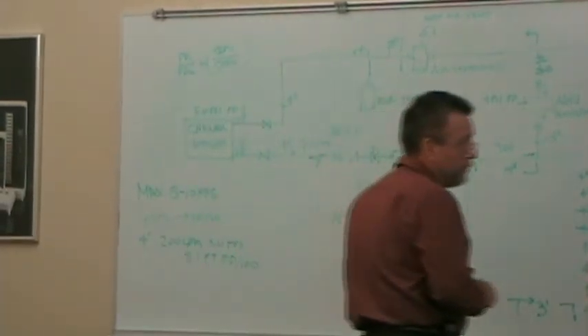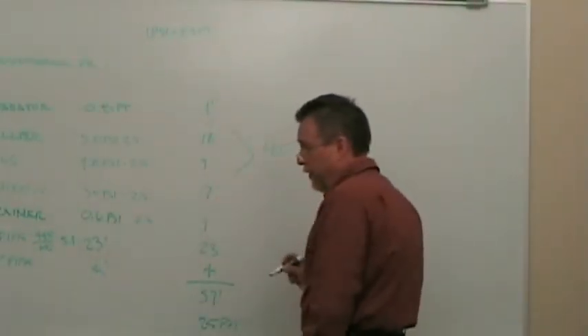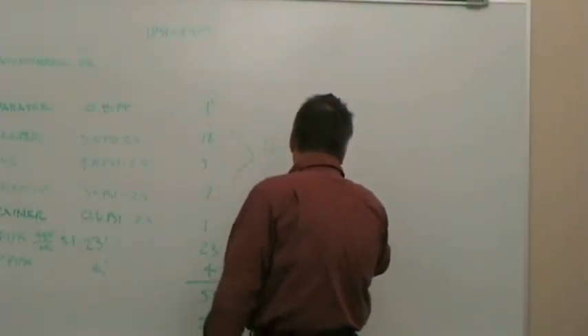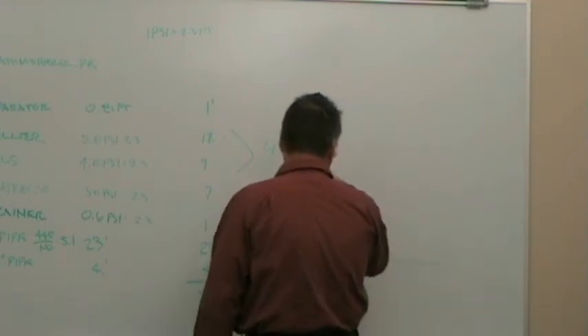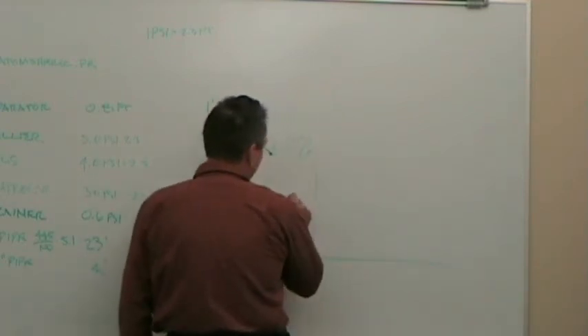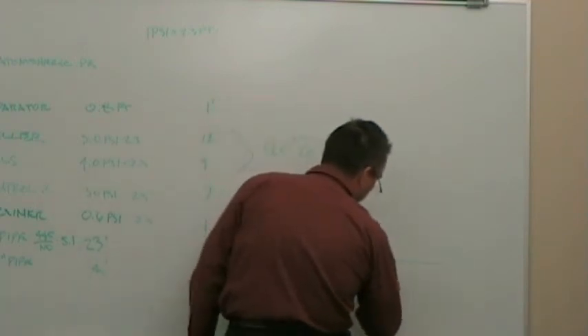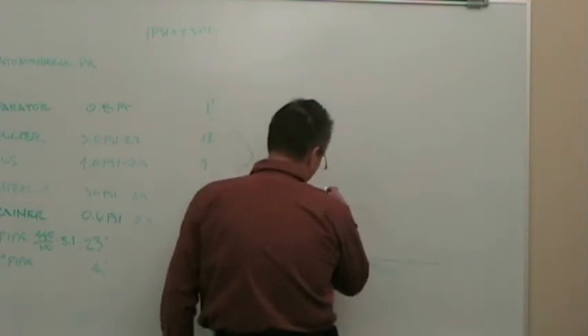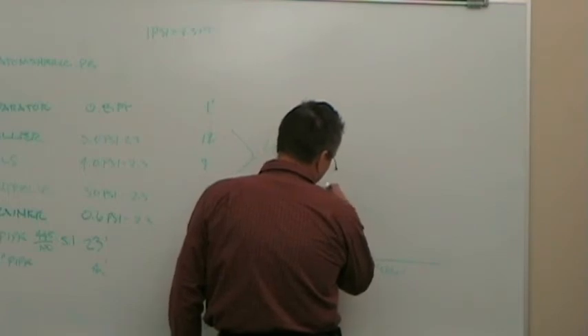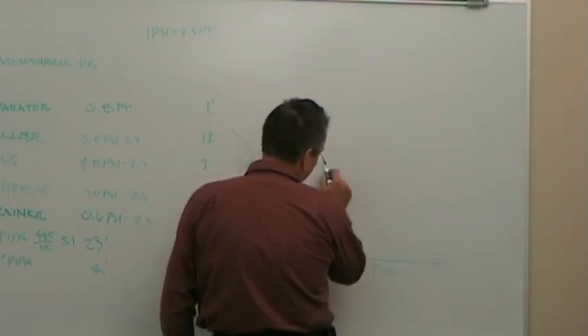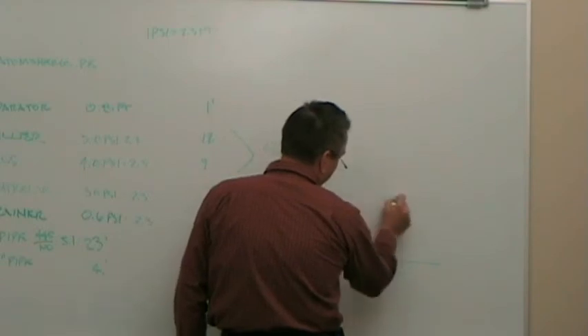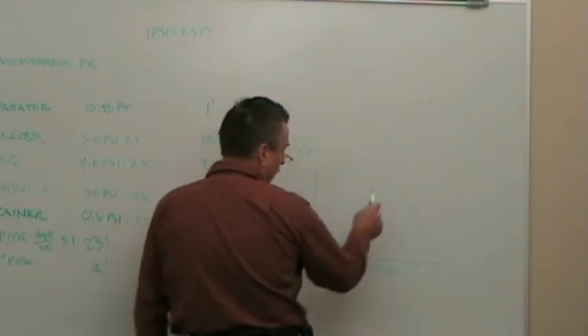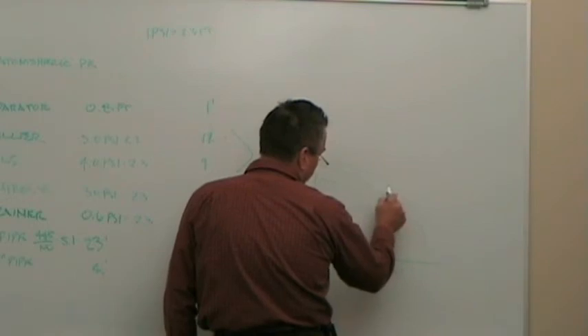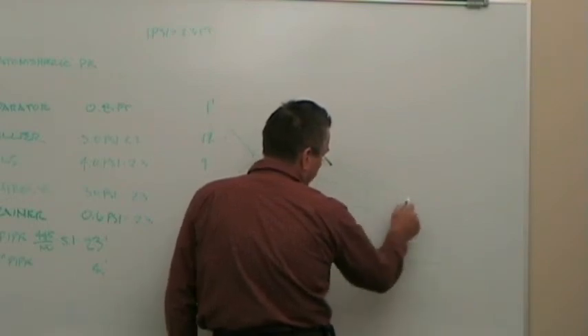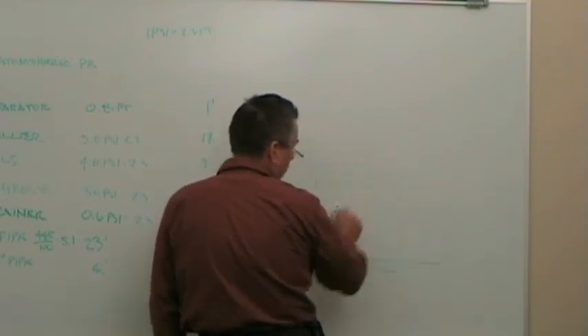I got to select these pumps. I don't have any pump curves because I don't have access to them. But a pump curve looks like this: we've got head and flow, and you've got impellers inside each pump that operate something like this. Then I'll have little circles in here that show me efficiency.